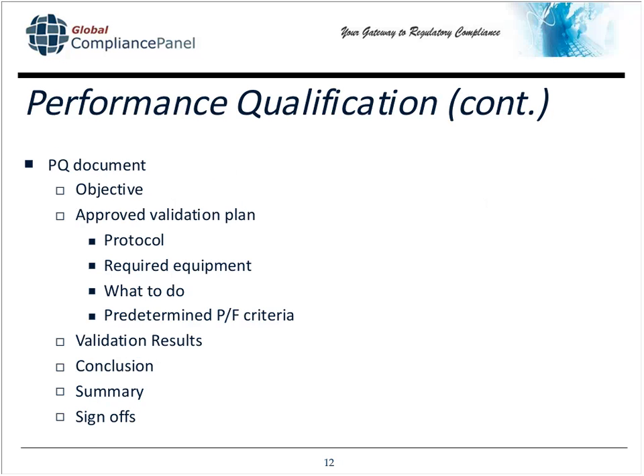The PQ itself, let me just say, this format should look familiar. The reason why is because consistency is the key. If you've seen that the OQ document is very similar to the PQ document, it enables your people in-house completing each document to be consistent, to know what to expect. The reviewers who review the validation plan as well as the validation results know where to look. And I would argue, most importantly, looking at the external reviewers, OEM partners, FDA, notified body, they've seen this before. All of your OQ and PQ documents look the same. So similarly, you have your signed-off validation plan and then your validation results document, including, as I mentioned earlier, the summary document for the reviewer.